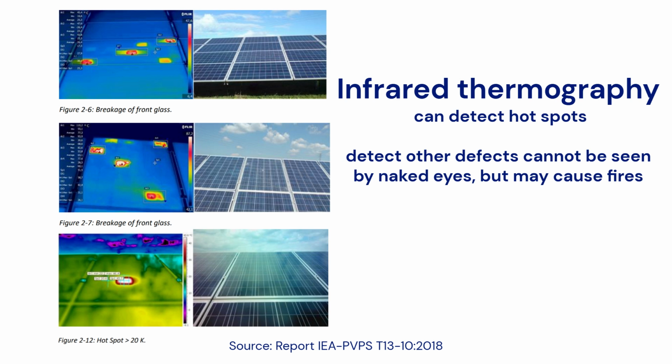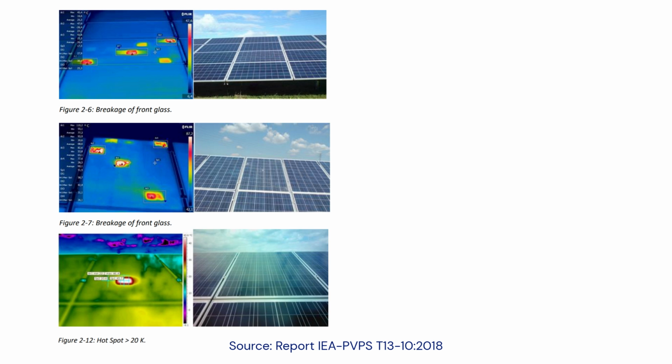Hot spots with strong local temperature gradients can significantly affect the performance of solar panels and, in extreme cases, may even cause smoldering fires. Infrared imaging is therefore a very useful tool to identify malfunctioning solar panels, module strings, and certain devices within a solar array, as long as external influences such as partial shading or dirt can be ruled out.